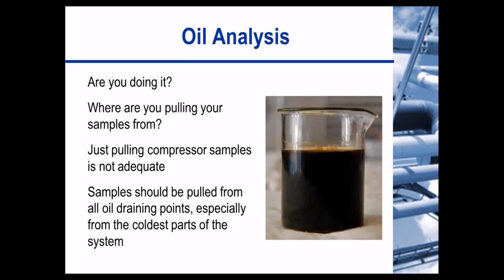So oil analysis: what exactly can it tell you and why is it important? Before we get to that, are you doing it, right? And if you are doing it, where are you pulling your samples from? Just pulling samples from the compressor is not adequate. Samples should be pulled from all oil draining points, especially from the coldest parts of your system. Both the oil analysis and the ammonia analysis should be part of that non-destructive testing program.